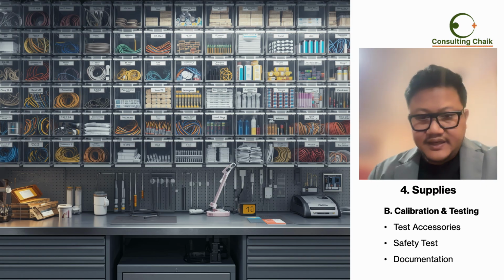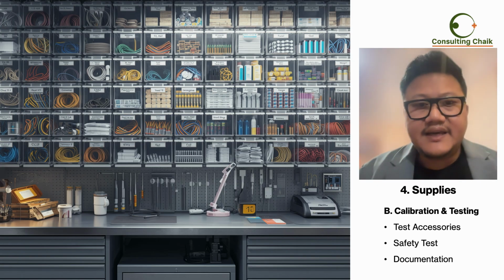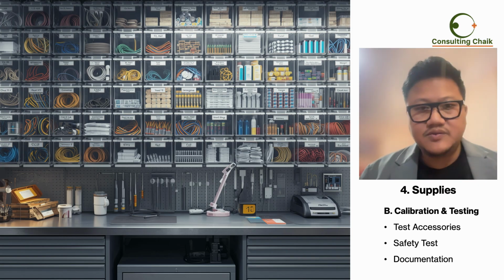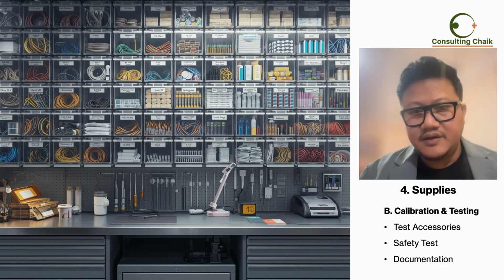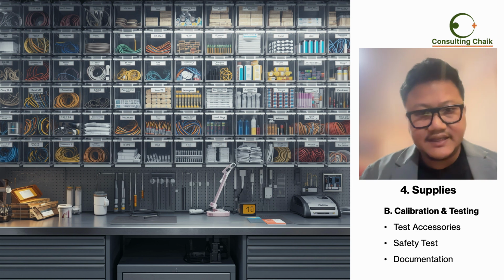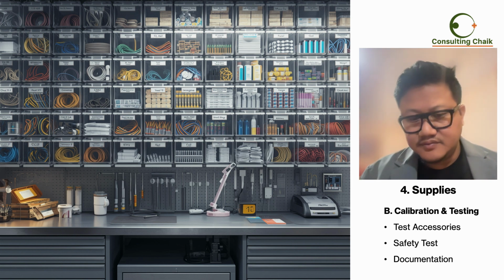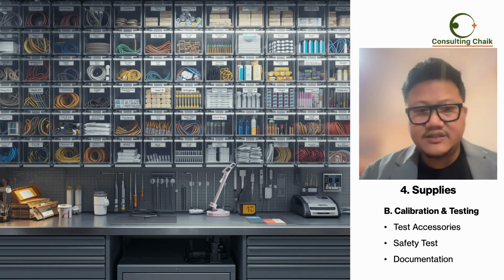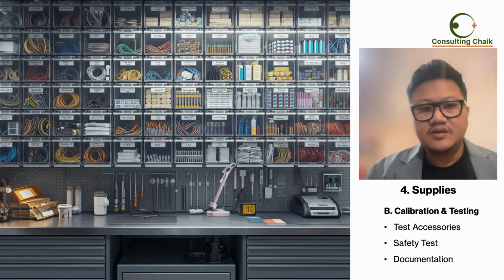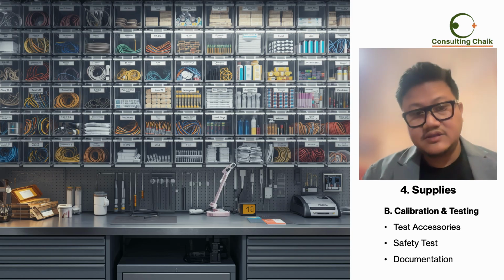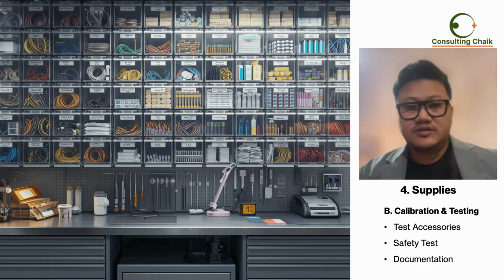Okay. Second one, calibration and testing. For this, you need test accessories like ECG electrodes, disposable packs, NIBP cuffs, single or multi-size, SpO2 sensors, calibration syringes. For safety test, you have test loads, different ohms, phantom simulators, calibration gases. Documentation, you need thermal paper rolls, asset labels, safety test tags, logbooks.